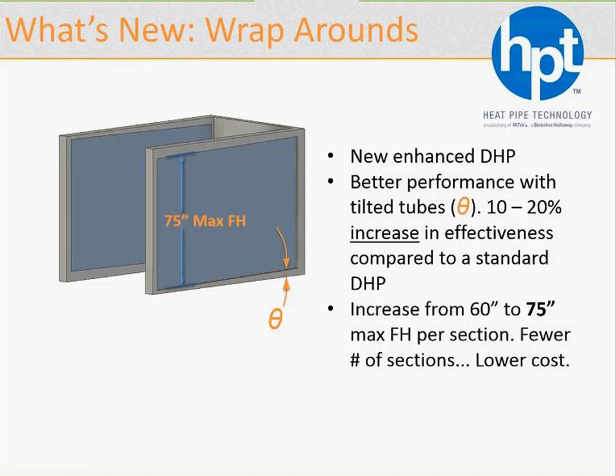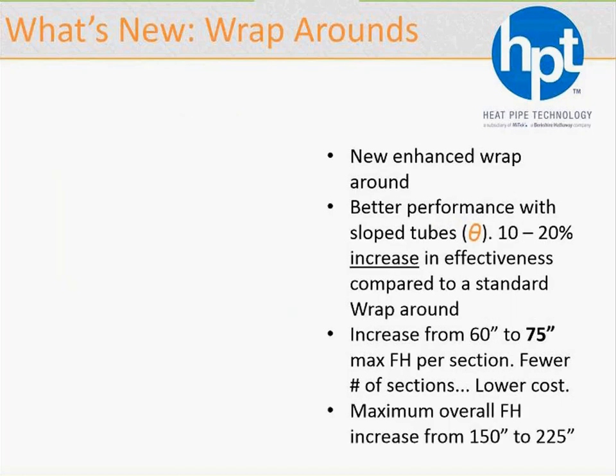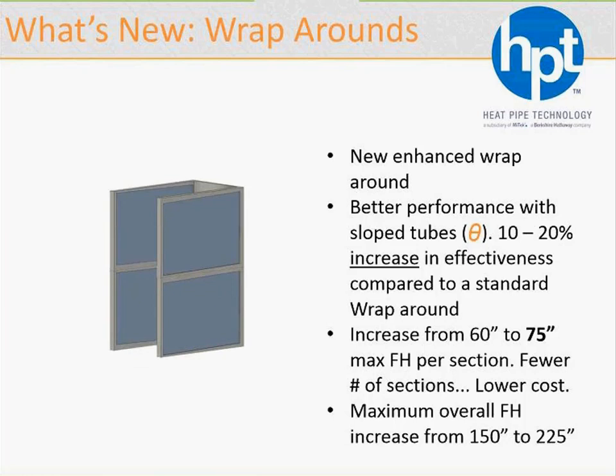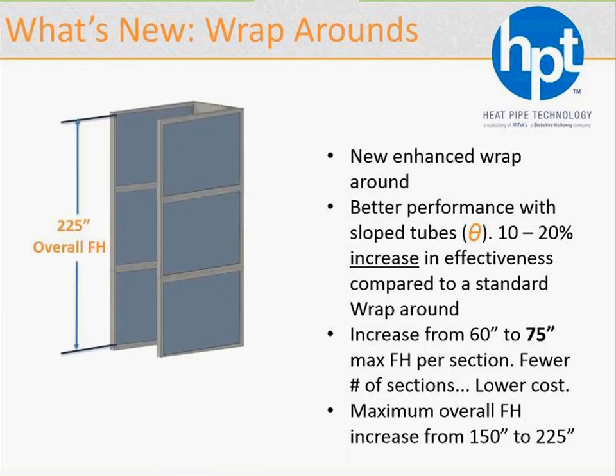One other recent development is we've increased the maximum height per section from 60 inches to 75 inches, allowing more heat transfer per cross-sectional area, less flanges, better performance, and less static. Also increased the maximum overall height from 150 to 225 inches, allowing more CFM. So basically you can get with this 75,000 CFM or higher even per system. 3 sections you can see. When you're looking at a large system, you start separating them into 75-inch sections. We can go up to 3 sections high.